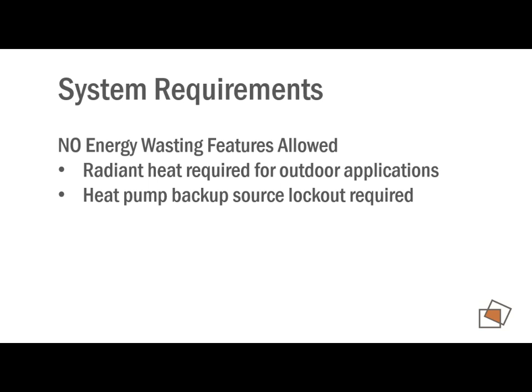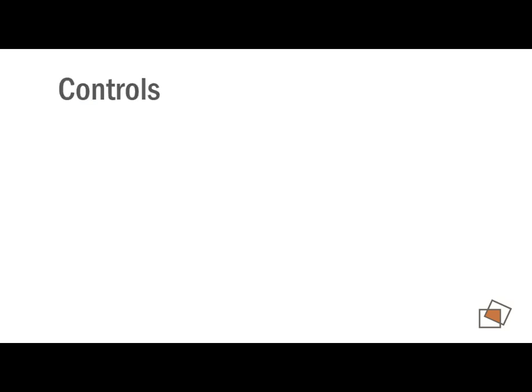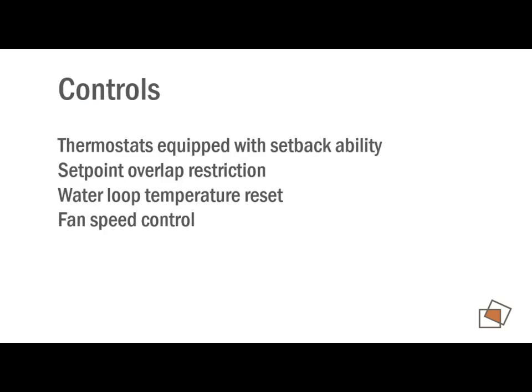So that's pretty obvious. And then there are some requirements associated with the controls. And really, most of your standard thermostats have this stuff built in nowadays anyway, but you have to use programmable thermostats that you can set back when the building's not in use. There's an overlap restriction, so you can't set the thermostat at 72 and the unit will heat and then cool and then heat and then cool, switch over and hunt all day. I think it's a 5-degree separation between those set points, so that it doesn't fight itself.